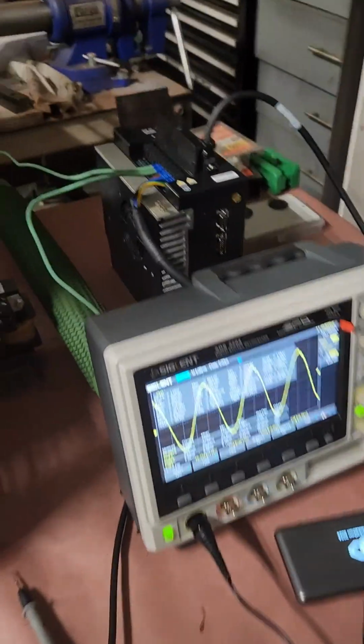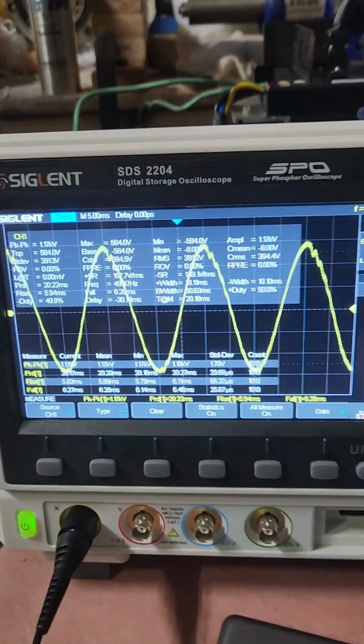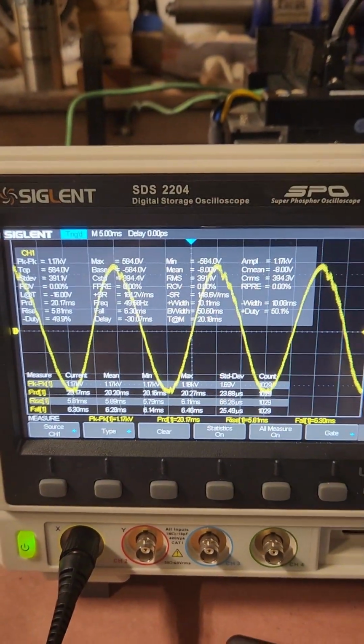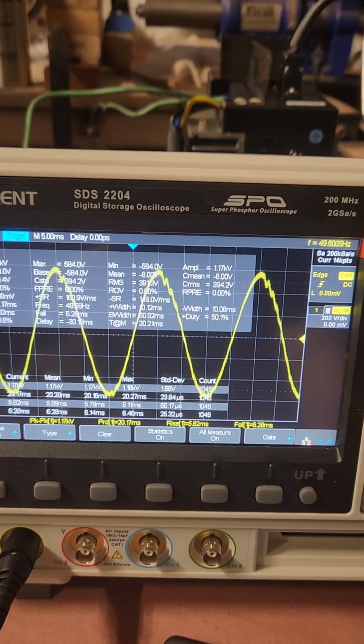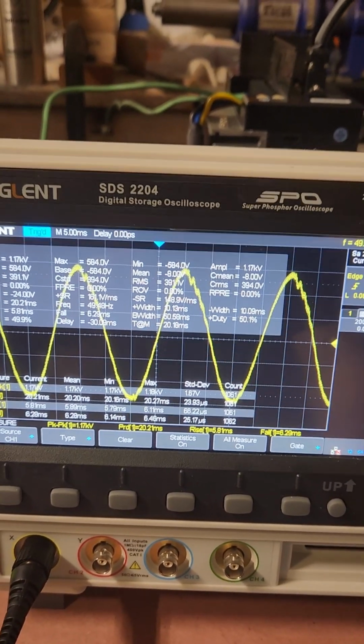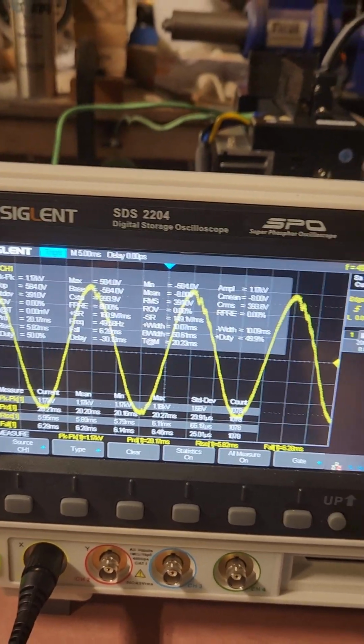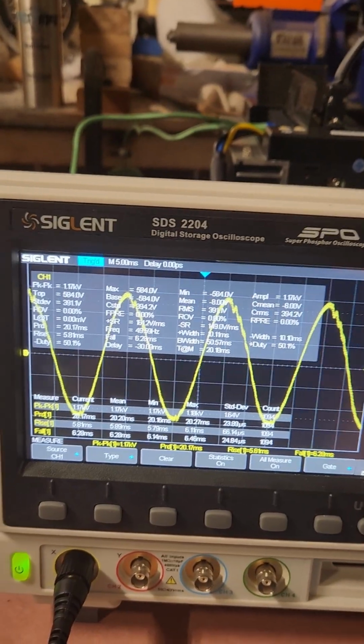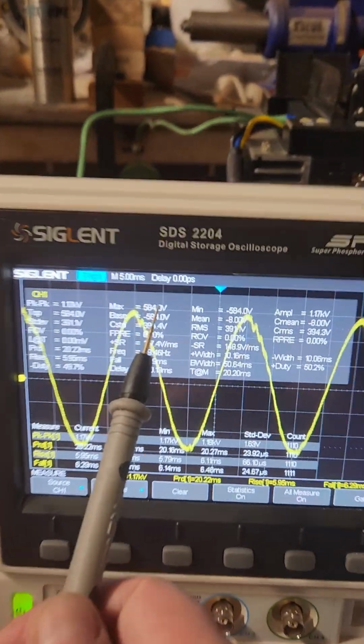So what I think I'll do is find a manual for this and adjust that VF curve, so I can set it up to reach 50 hertz at exactly 380 volts, or maybe even lower, 5 to 10%, so that peak doesn't get to 584.